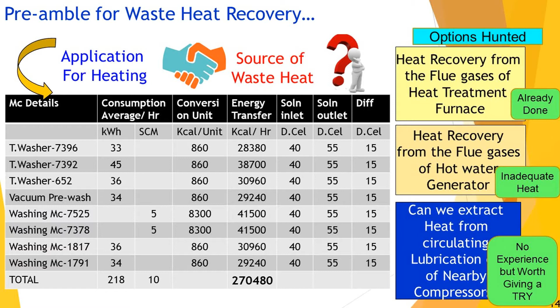We wanted to find out the source of waste heat, so we explored and hunted where we could get it. One option was heat recovery from the flue gases of the heat treatment furnace, which is already done. Could we extract heat from the flue gases of the hot water generators? That was not adequate heat. So we wanted to give a try to extract heat from the lubrication oil of the nearby compressors. We never tried this concept before, but we wanted to give it a try.